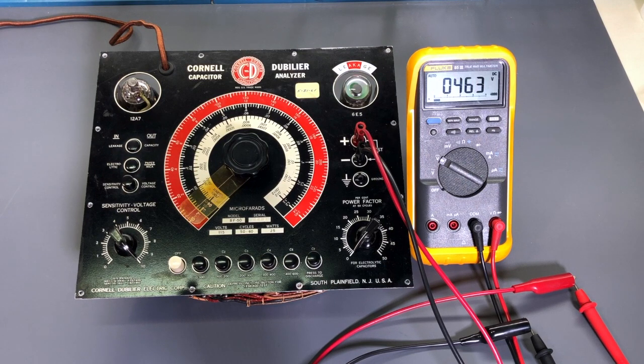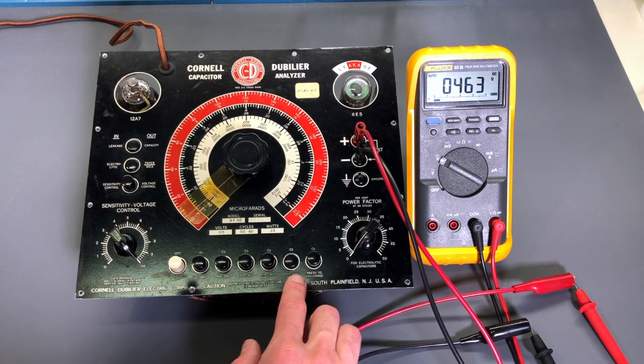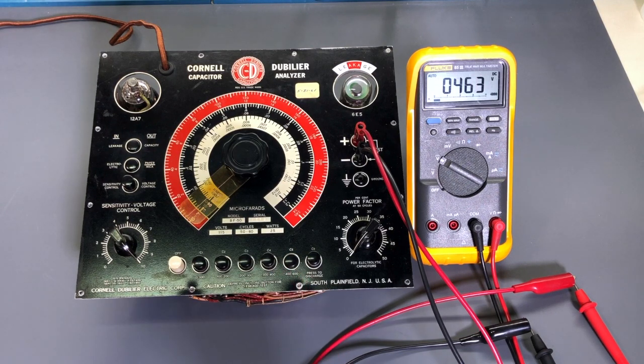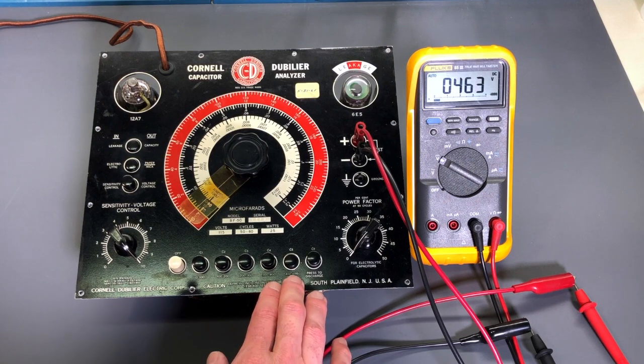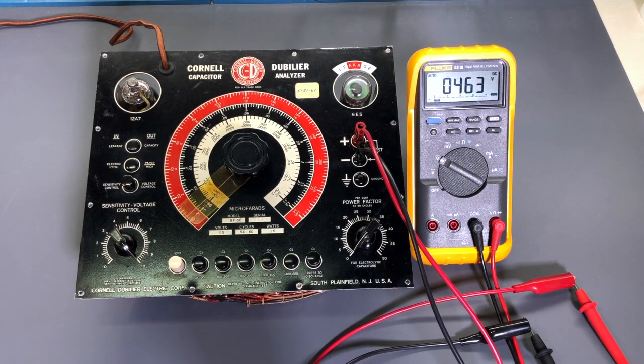So very reasonable. Again, the manual mentions that this does not go to 600 volts. It's interesting that they printed 600 on there, but it actually doesn't go to that range. But 463 volts, which is about, I believe, the B+ maximum. So those values are looking very good. So I'll reposition the tester now and connect a capacitor across the test jacks, and we'll do a leakage test.